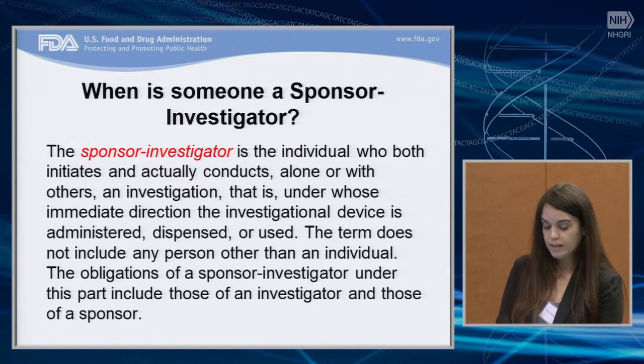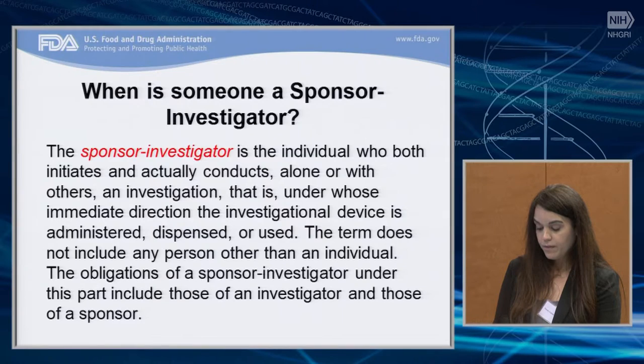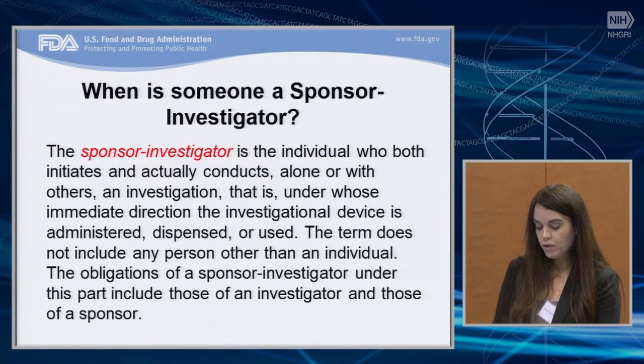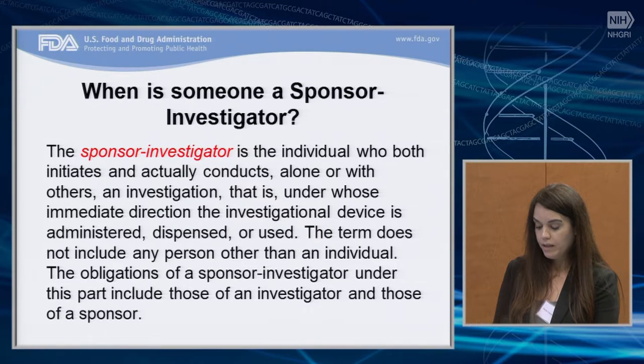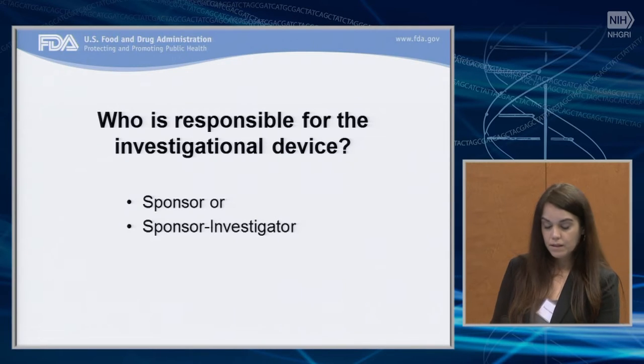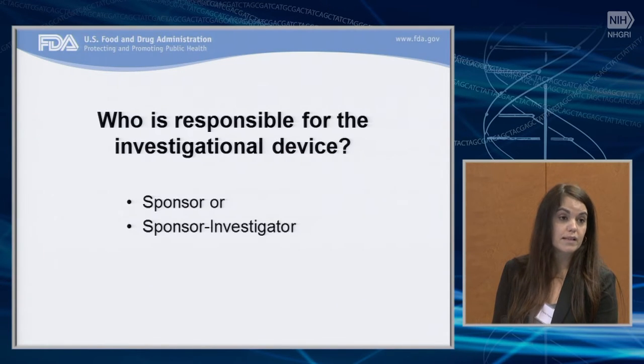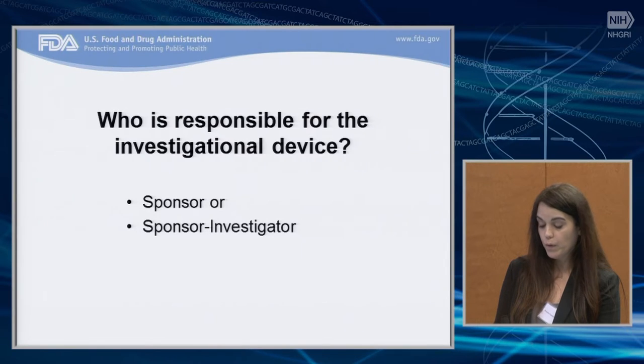The third possibility is the sponsor-investigator. The term is defined in the IDE regulations as the individual who both initiates and actually conducts, alone or with others, an investigation — that is, under whose immediate direction the investigational device is administered, dispensed, or used. The term does not include any person other than an individual. The obligations of a sponsor-investigator include those of an investigator and those of a sponsor. The sponsor or sponsor-investigator is responsible for the regulatory requirements of the investigational device.